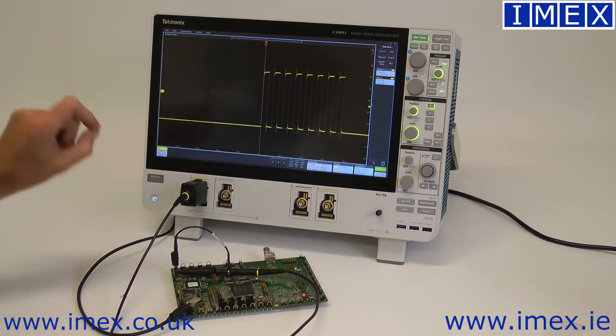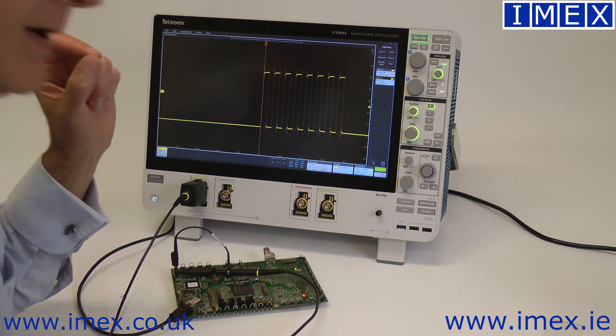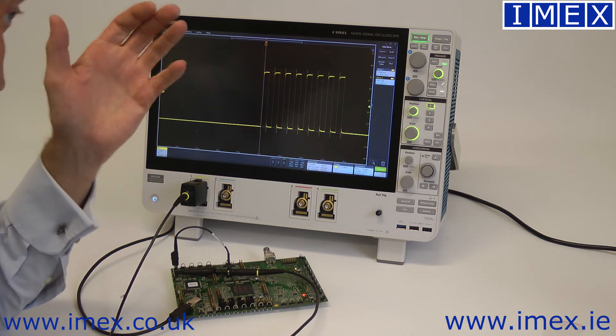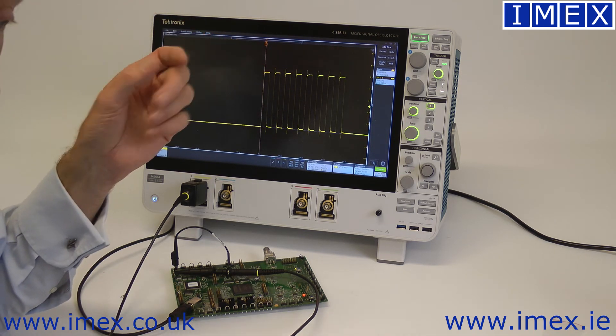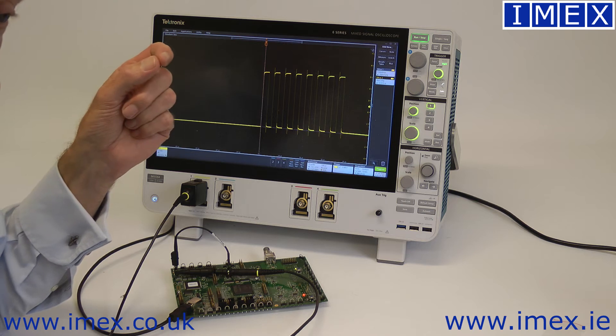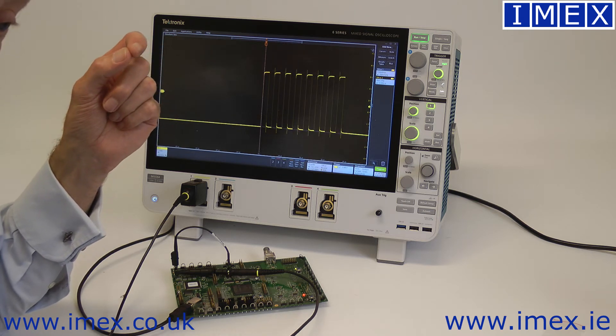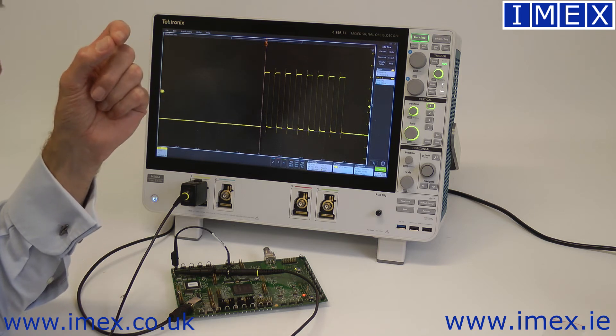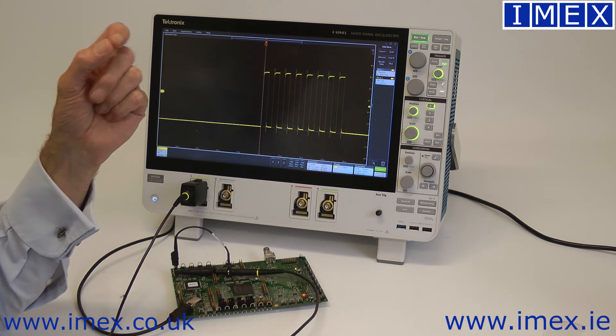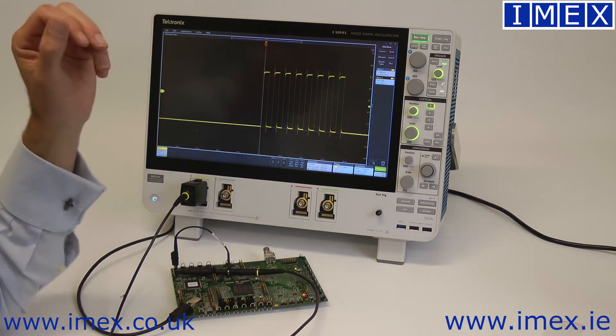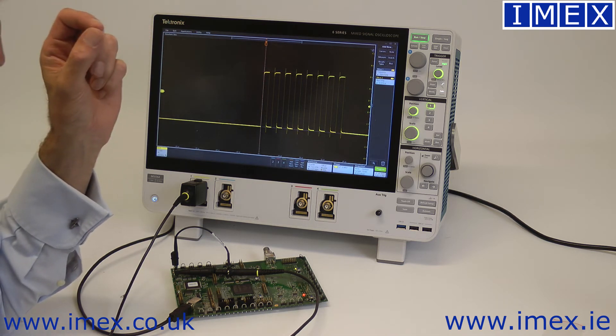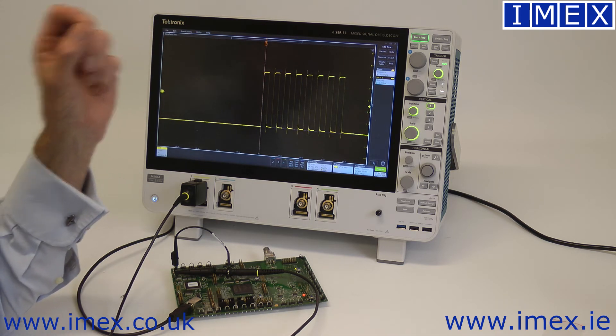We need to understand about bandwidth and rise time. There's a simple formula which equates the two: 0.35 divided by the bandwidth gives you the rise time of the instrument. It depends on the input shape of the filter, but as a rule of thumb, 0.35 divided by bandwidth equals rise time.